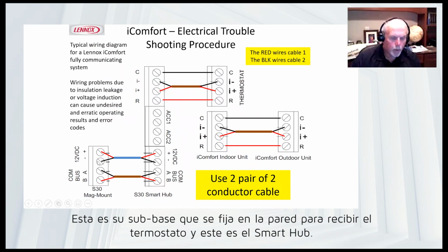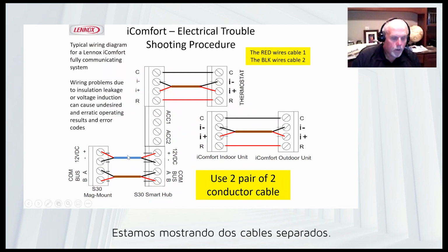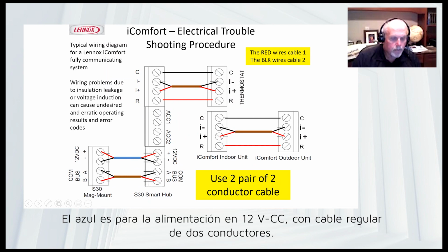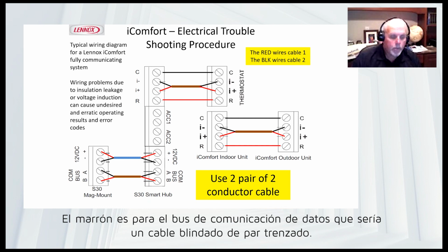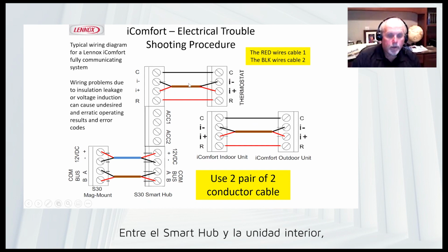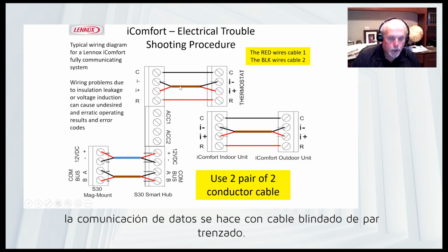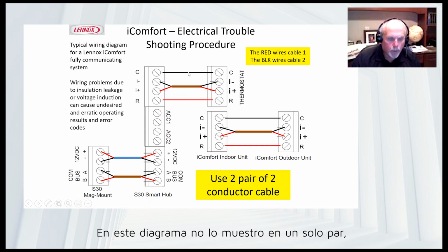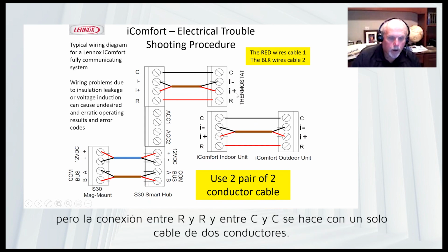Okay, this is your sub base, up on the wall. And this is the smart hub. So we're showing two separate cables, one for the 12 volt DC, that would be your regular thermostat wire, and then one for your communication bus, and that would be your shielded twisted pair wire. From the smart hub to the indoor unit, on the communication bus, shielded wire, and I couldn't put them in one jacket showing one cable, but the two outer wires here, R and C, are one cable, and that could be regular thermostat wire.